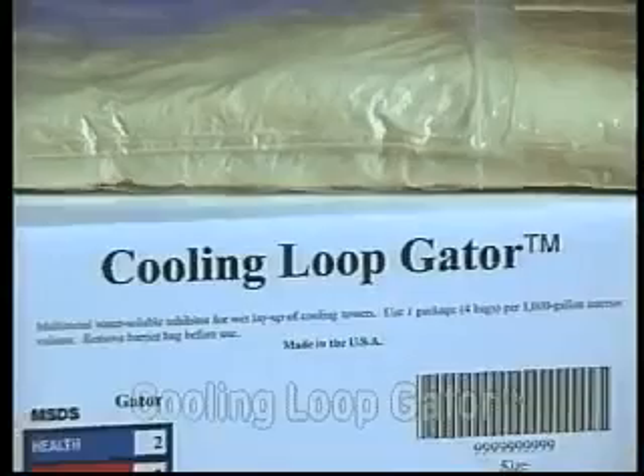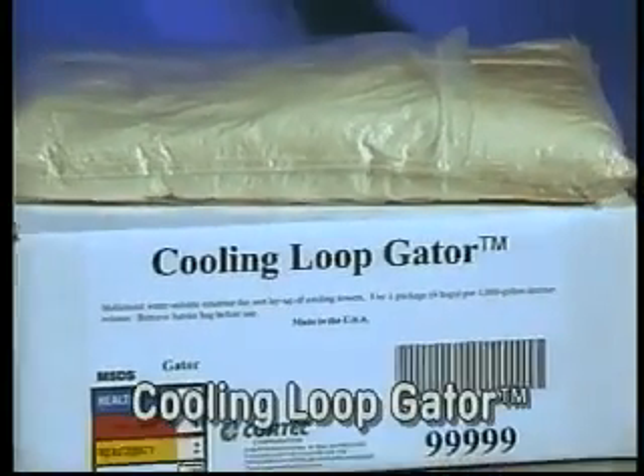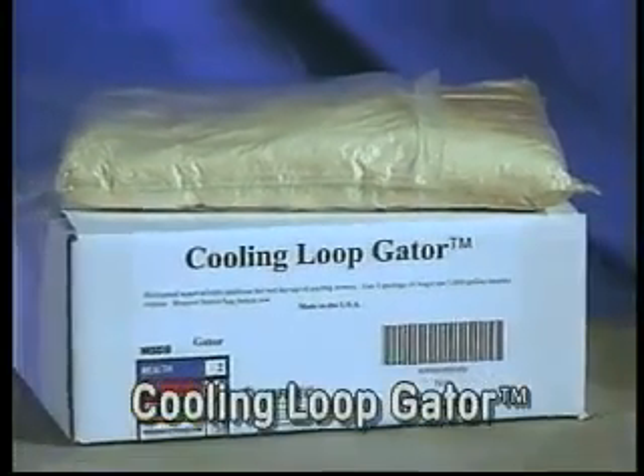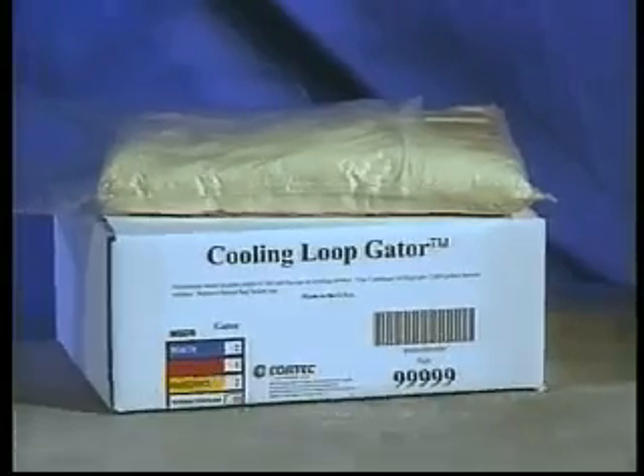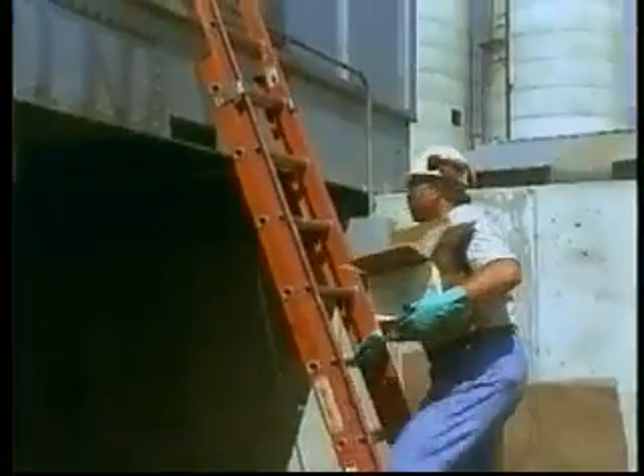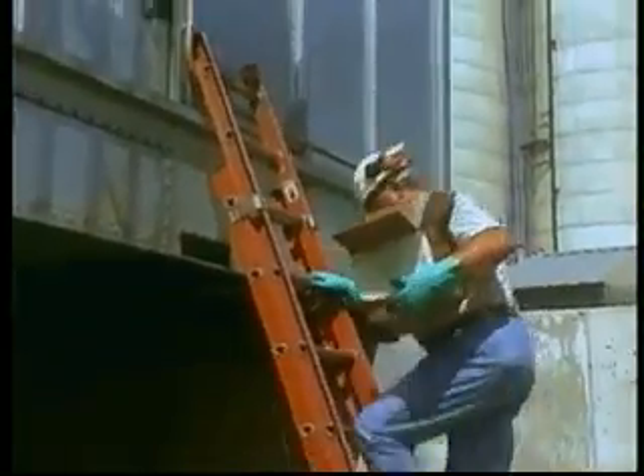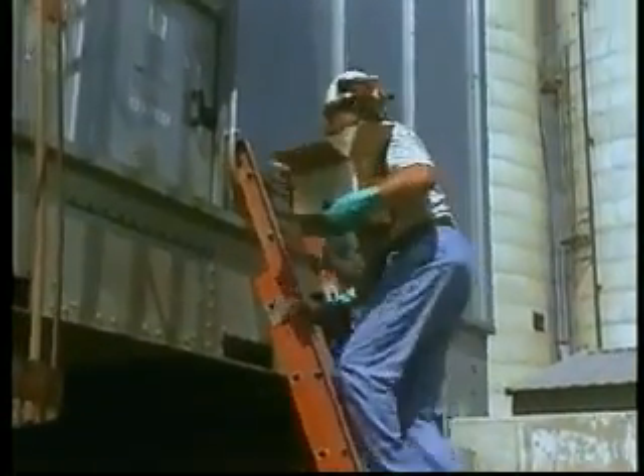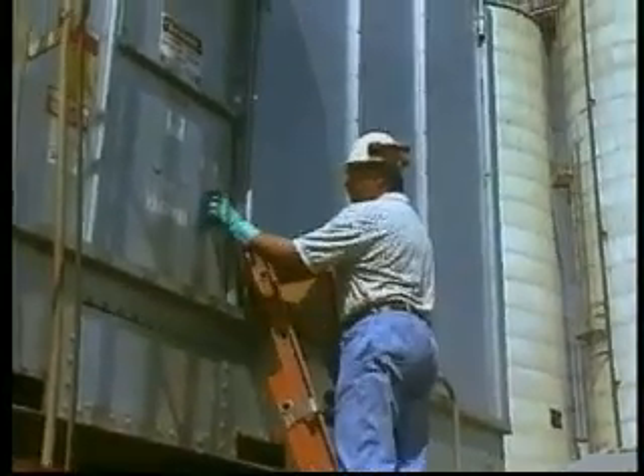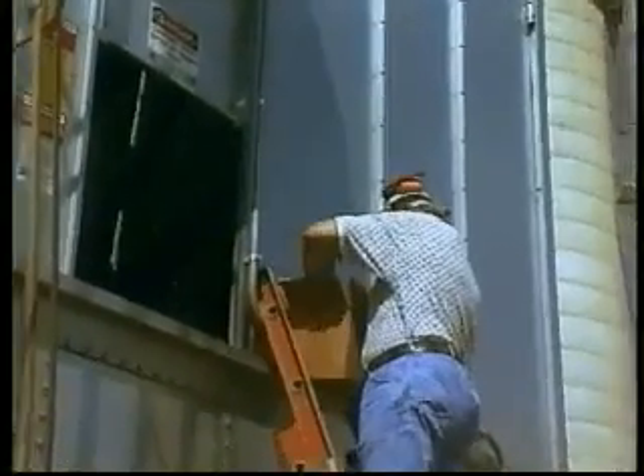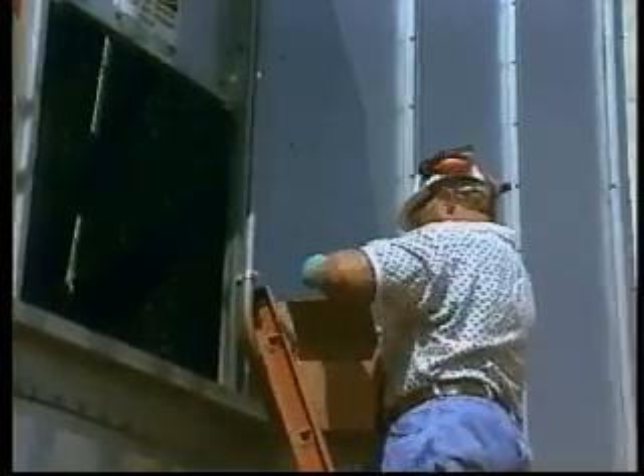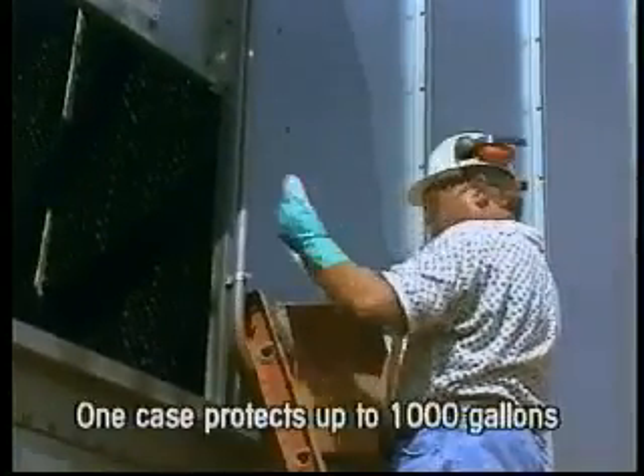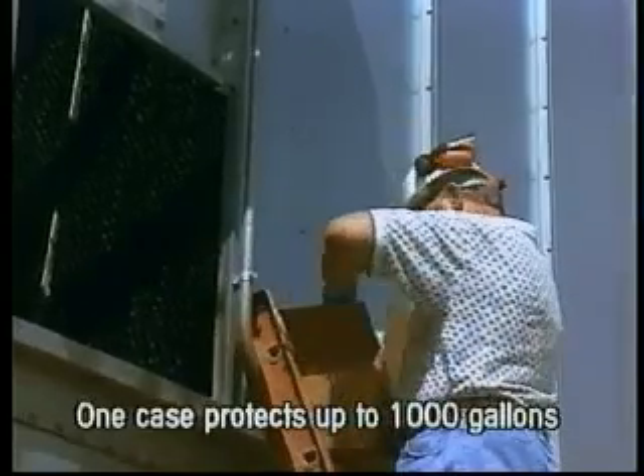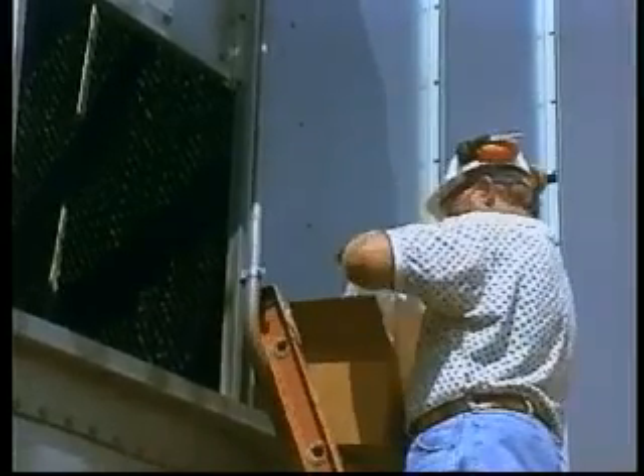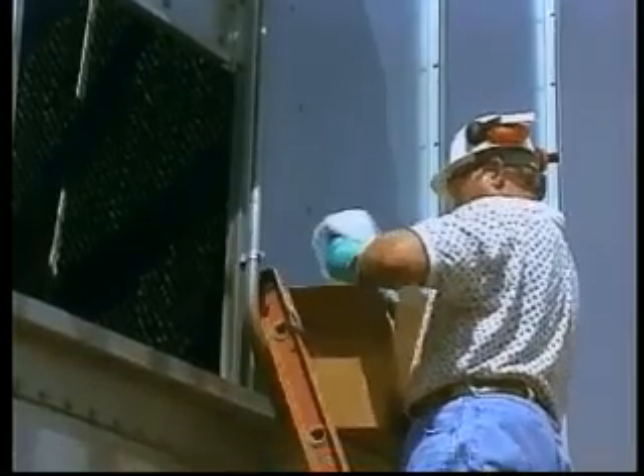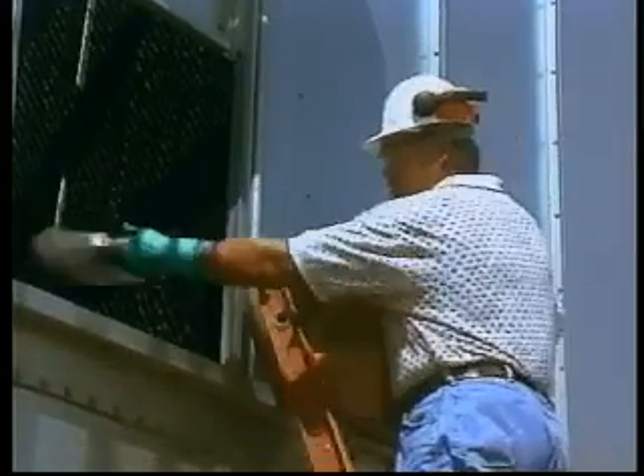Cortec's next layup animal is the cooling loop gator. Just like its name, it's ideal for the layup of cooling towers. Cooling loop gators employ the same water-soluble bag packaging for easy application. Each cooling loop gator weighs only 2.2 pounds and can protect up to 250 gallons of water. One case of cooling loop gators protects up to 1,000 gallons of system volume. To apply the cooling loop gator, simply toss directly into the cooling tower and circulate.